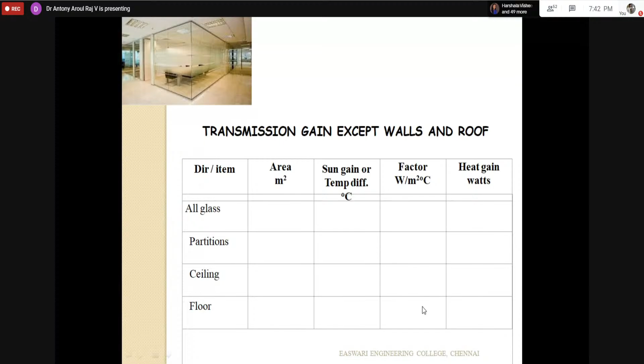Then infiltration and ventilation, the sensible component. What is the infiltration quantity? Put the bypass factor, what is the density, what is the volume flow rate, what is the specific heat, what is the temperature difference. I told you MCP delta T, but it is multiplied by bypass factor. What is the heat gain in watts? That I am putting here.